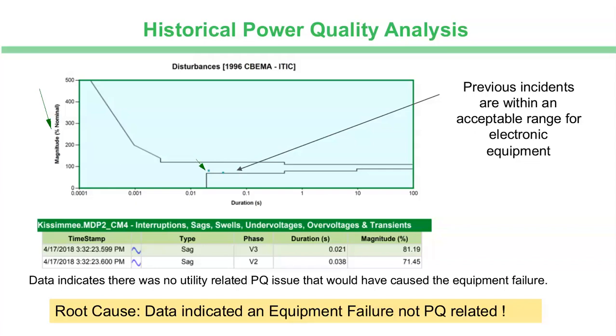And so systems that include sensitive electronics can withstand short duration events, but the longer the event, the lower the magnitude that can be ridden through. But what we see in this particular plot is that all of the power quality events that had been observed are within that envelope of acceptable power. So according to the data, the equipment failure in this particular case was not a result of power quality.